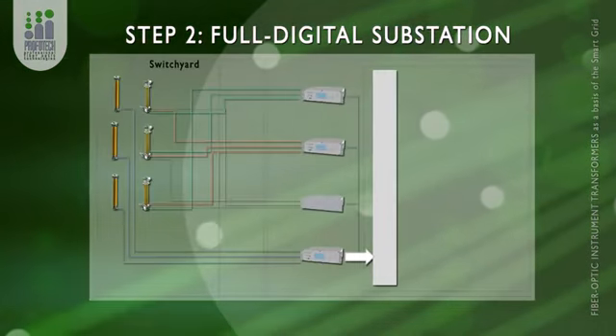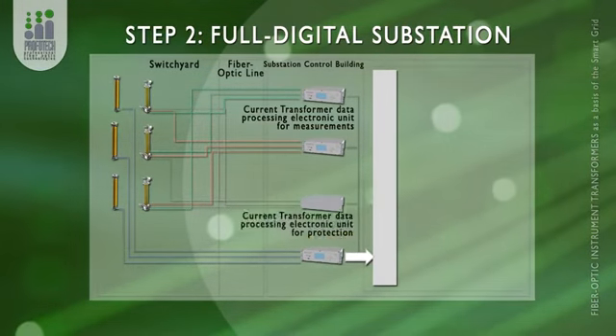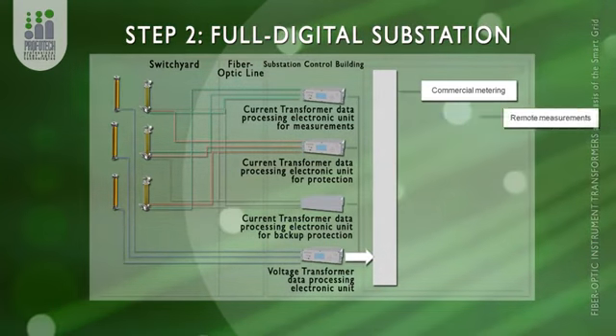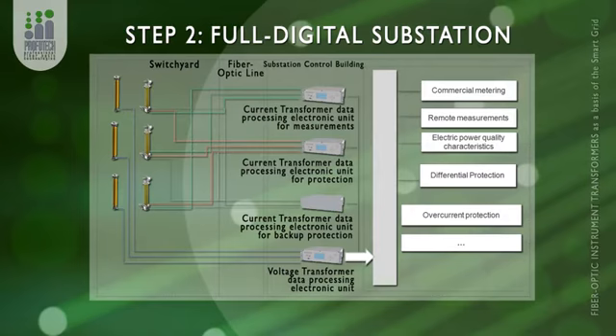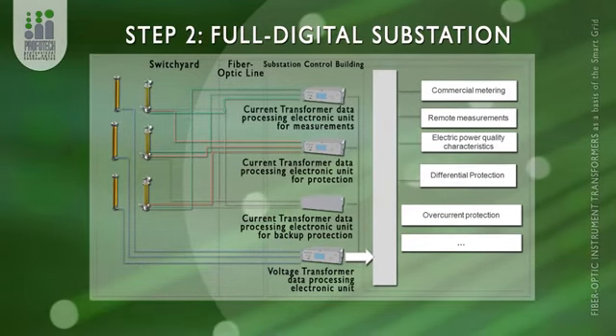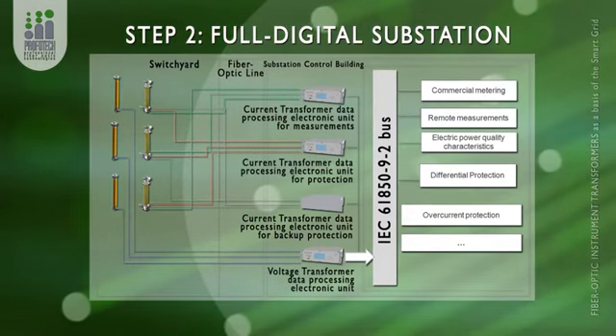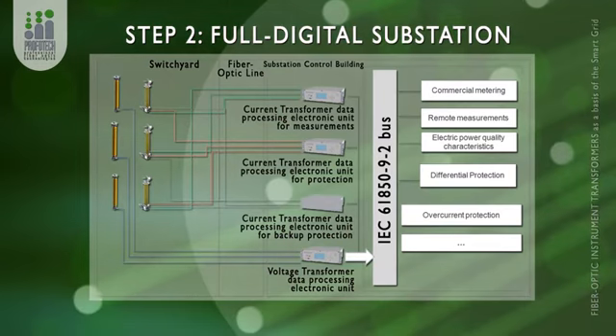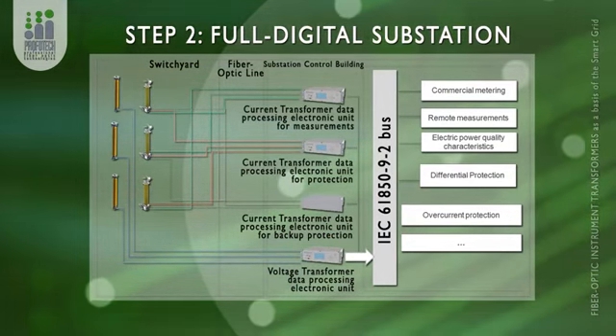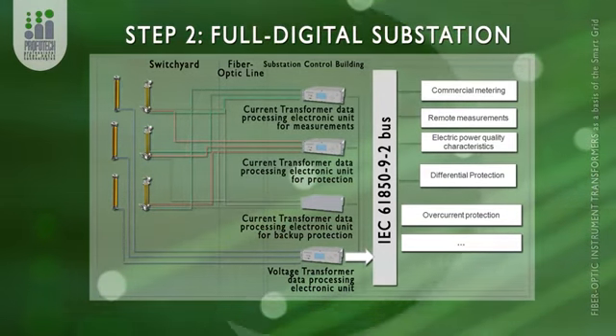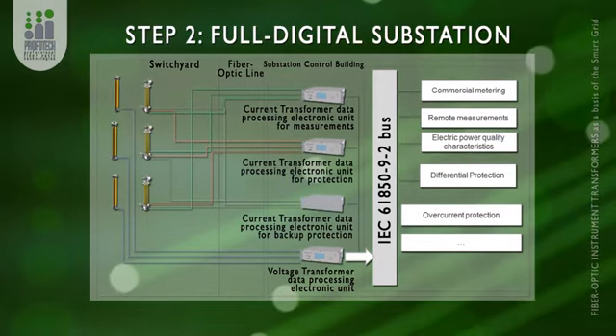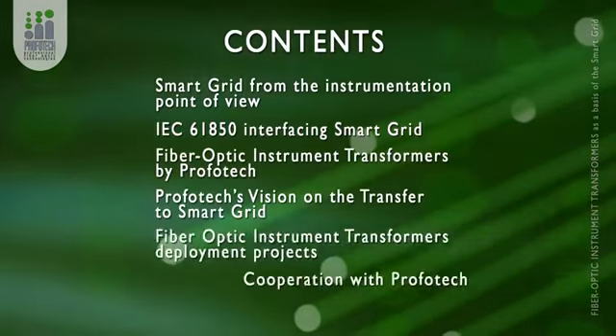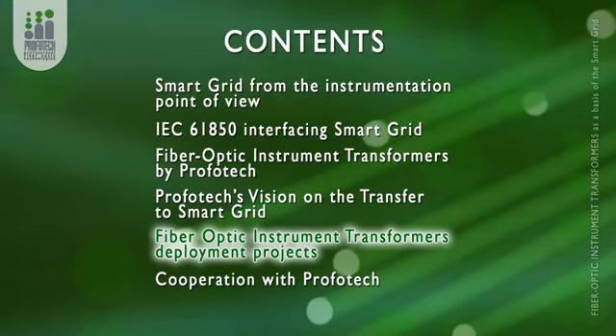This is a fully digital substation where the sensors are already installed. You do not need to change them. Simply use them and add other electronic modules. By doing this, we form the full IEC 61850-9-2 process bus where you can connect any secondary equipment. This is the revenue metering which we have in the first step. This will provide for the protection and control for power quality monitoring of any secondary equipment. And by the way, there are many secondary equipment options available with the 9-2 interface, so this is not a real issue.